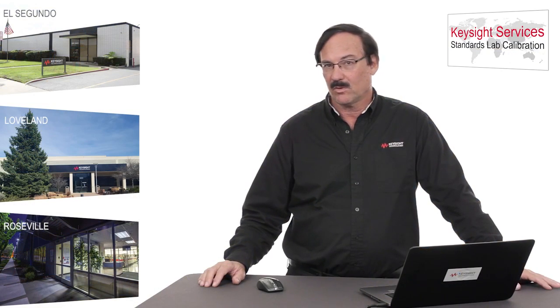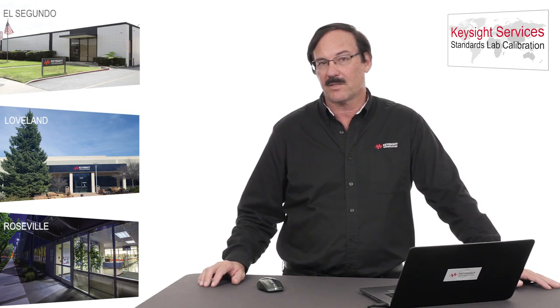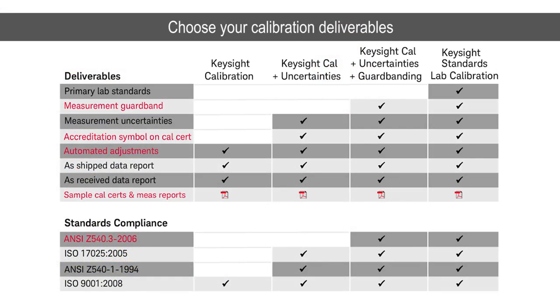Before I leave, I'd like to review the key deliverables that you'll receive regardless of which discipline we are operating in, both the calibration report and the calibration certificate. So let's just take a look here at the table. You can see the Keysight Standards Lab calibrations on the right-hand side. The first row, primary lab standards. What distinguishes these from our other calibrations is that we use either a primary standard or one step removed from a primary standard. That's where we get the really good accuracy and the really low measurement uncertainties.